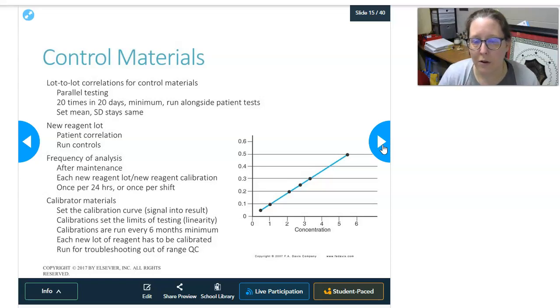So they are responsible for turning the signal, the absorbance, into a concentration. If you remember, we had set a calibration line here, where a set absorbance equals a specific concentration. And if you move the line up or down, then it changes what the absorbance would translate as, which concentration it will mean.